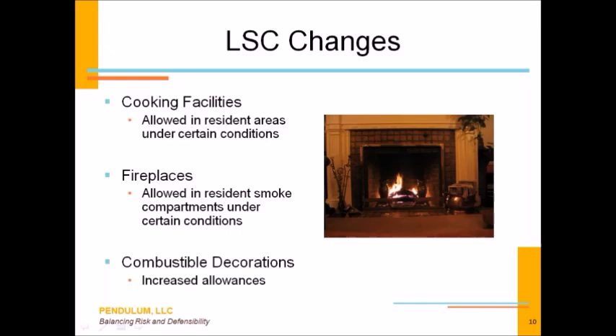Same thing with fireplaces. There are some allowances for fireplaces to be within a patient care area, within a specific smoke compartment, providing that there are certain elements like smoke detectors, protection in front of the fireplace itself, and the presence of carbon monoxide detectors and other things. When it comes to combustible decorations, I probably should have put a chart up on this one, but there are definitely some relaxed requirements. As you all know, previously, everything needed to be non-combustible, everything needed to be treated, and it needed to be limited.